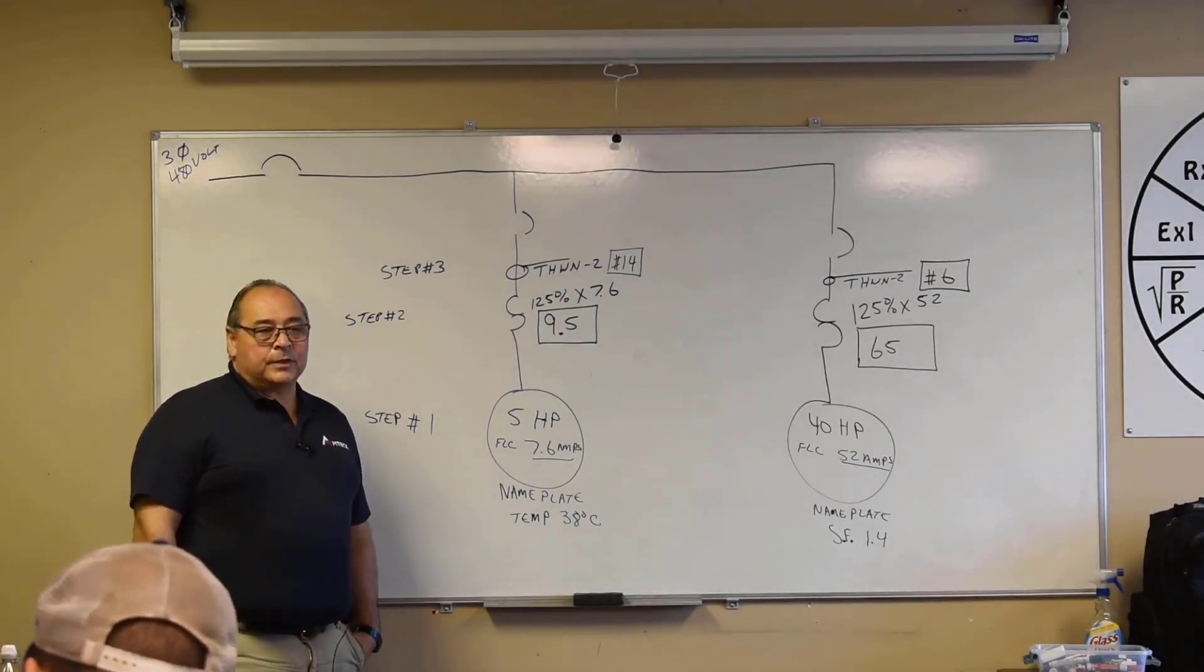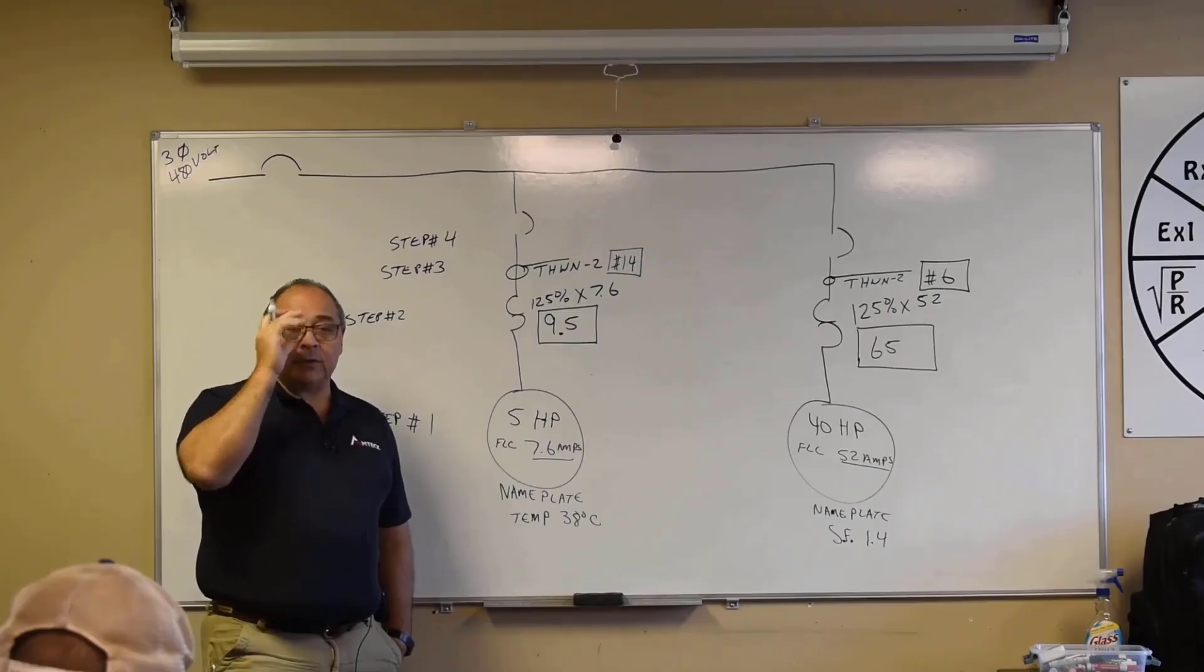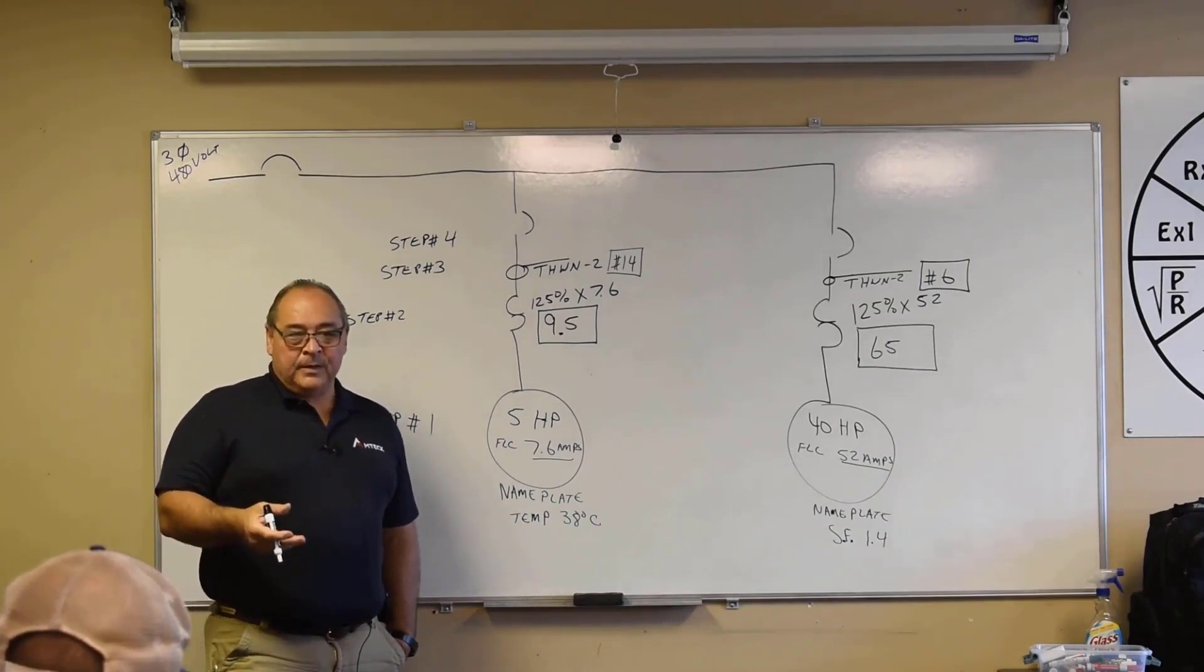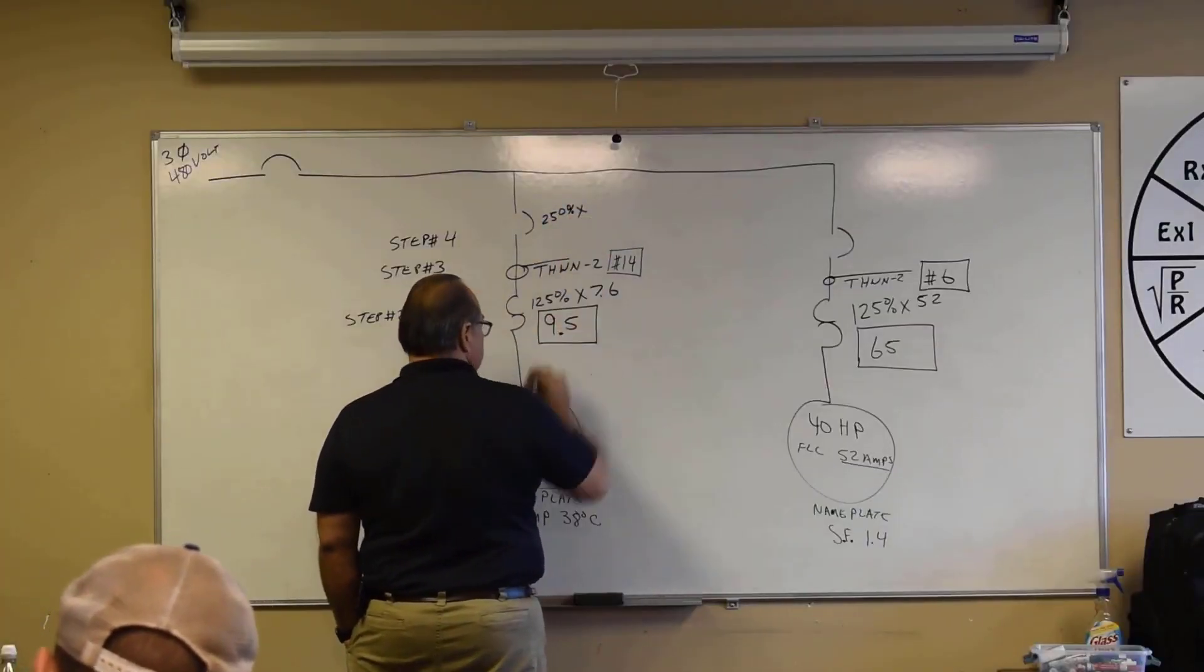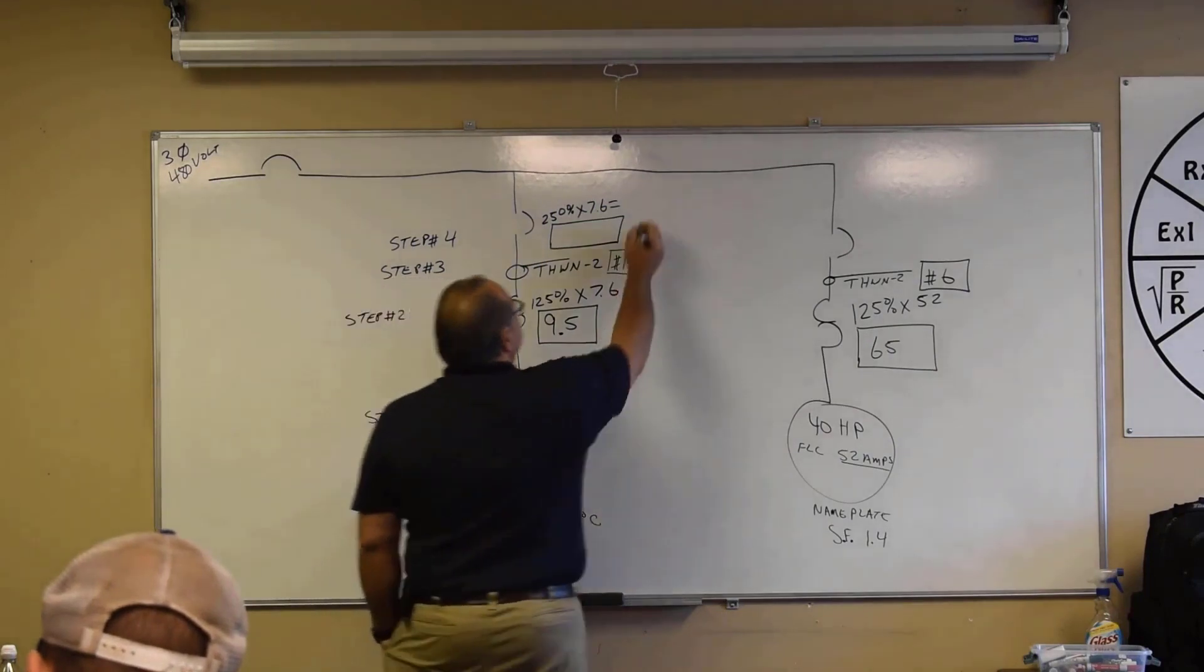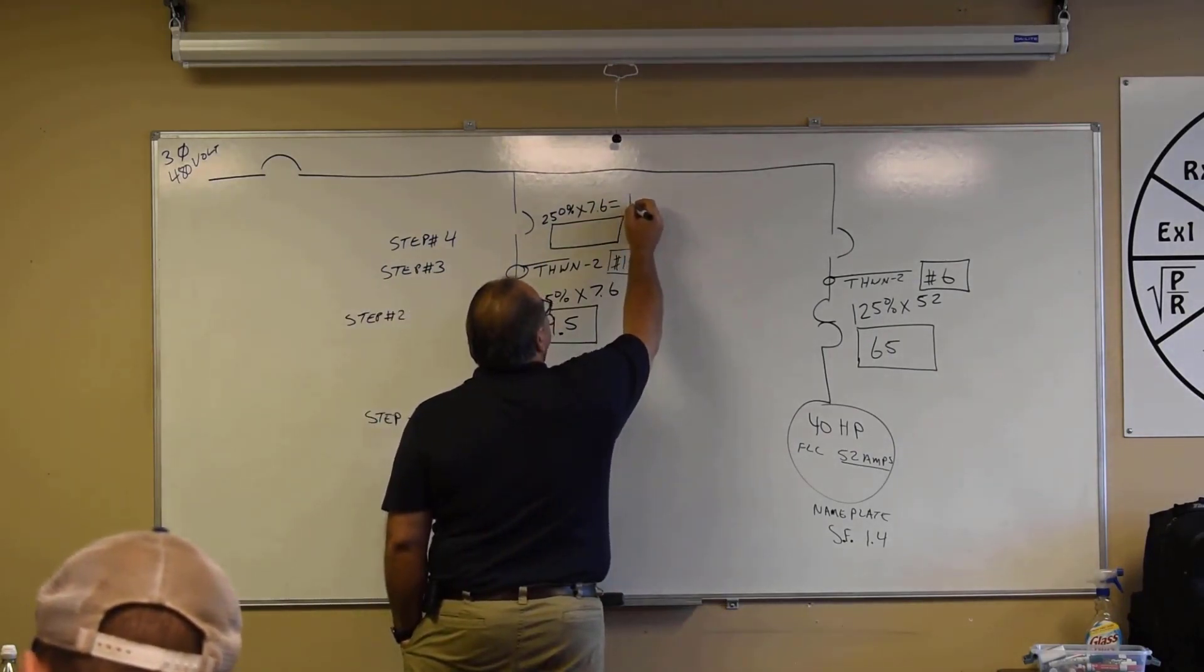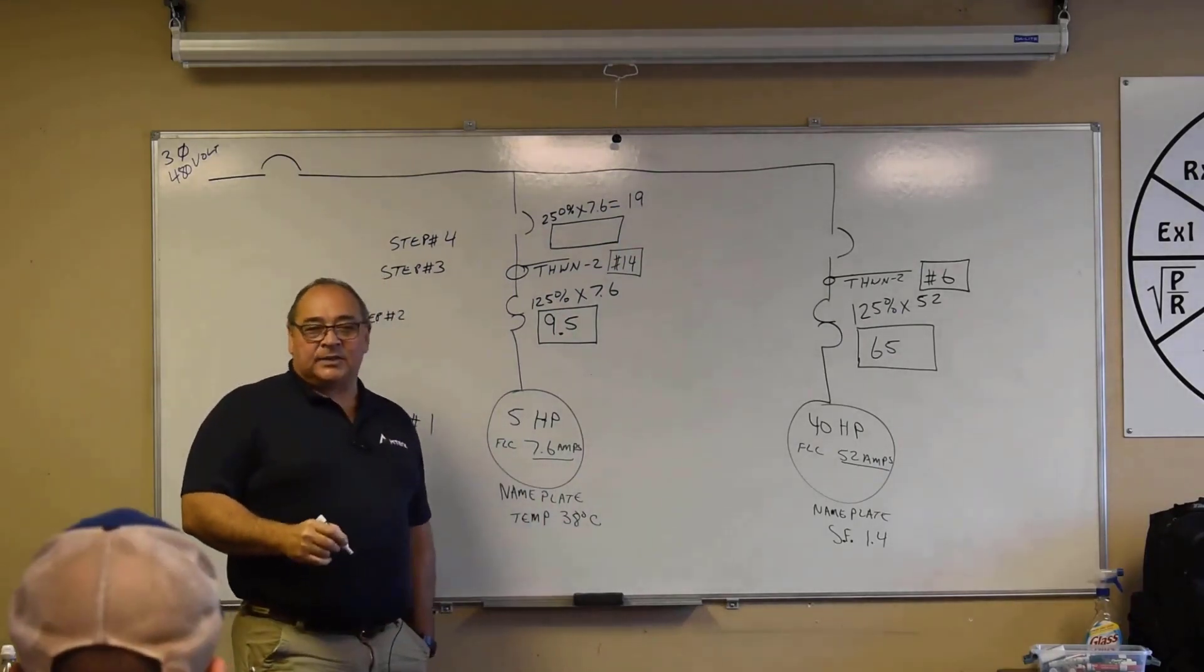Then the test question will provide you with which style fuse or circuit breaker we're going to use for step number four. So step number four sizes that fuse or circuit breaker. Since we actually have a symbol that represents a breaker, we'll use the inverse time circuit breaker, which is a standard everyday circuit breaker. What is our percentage for that? For an inverse time circuit breaker, 430.52 table, not an instantaneous trip, but the inverse time, 250 percent, right? So 250 percent times our full load current, remember, 7.6, right? What's that equal? 19, even got me some change. 19 even. All right, he's good. So 19 is not a standard fuse or circuit breaker size. Well, what can we do? What do we got to do?